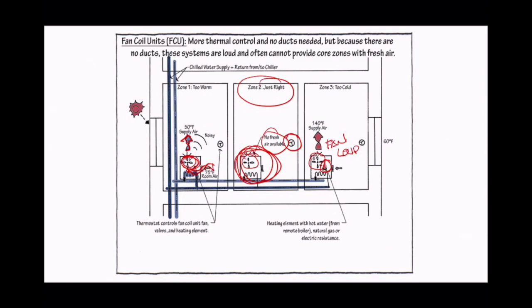If you have a theater or a gym in the school, that space may need its own single zone, because you don't want the classroom sharing air with the gym. The gym gets hot and sweaty from people moving around, so we don't want that air recycled into the classroom or vice versa. It wouldn't be a VAV exactly, but it would be a ducted system like a VAV for the gym—just a single fan in some other room, with the duct running down the hallway to service the gym.